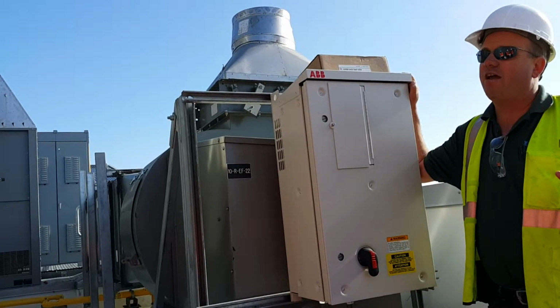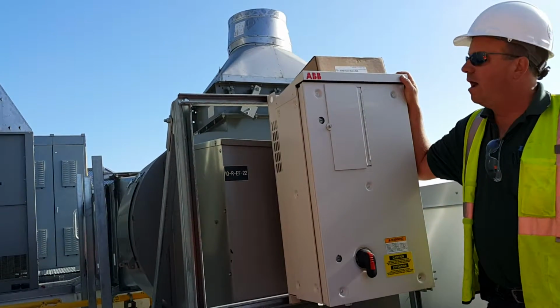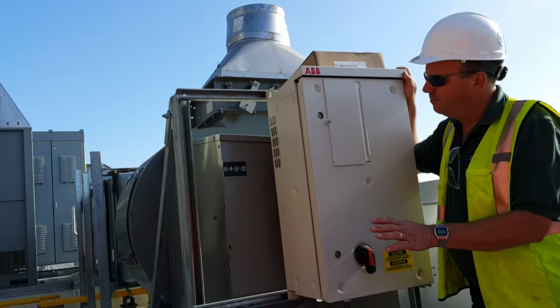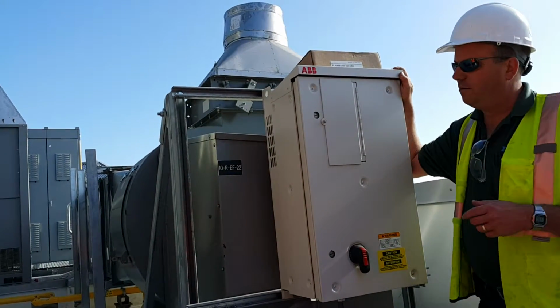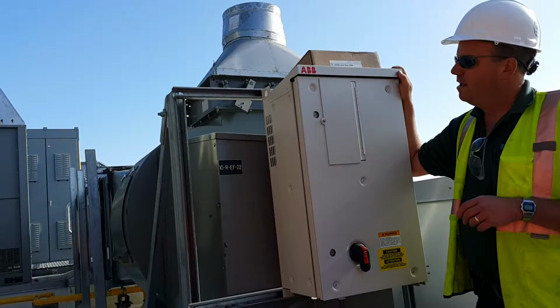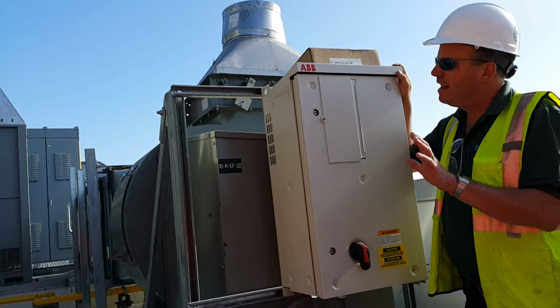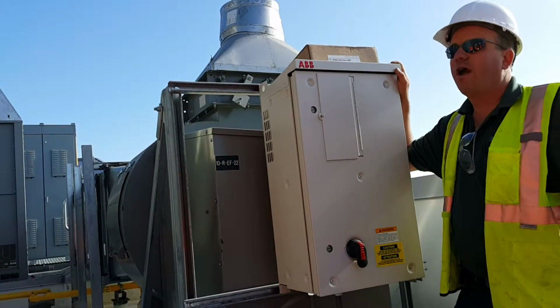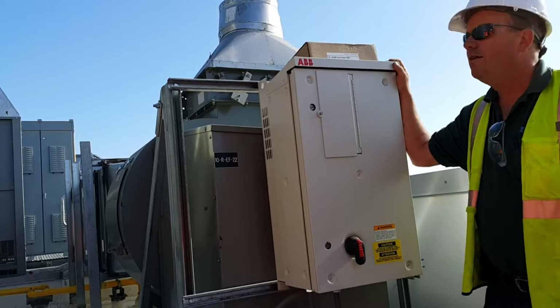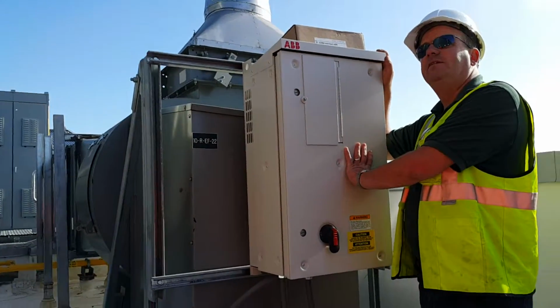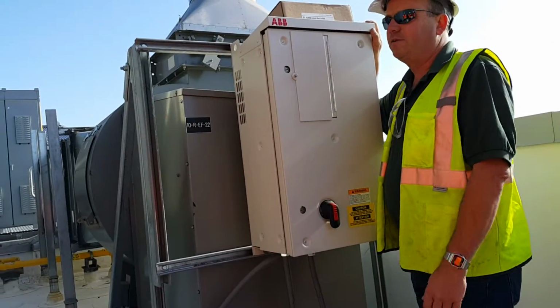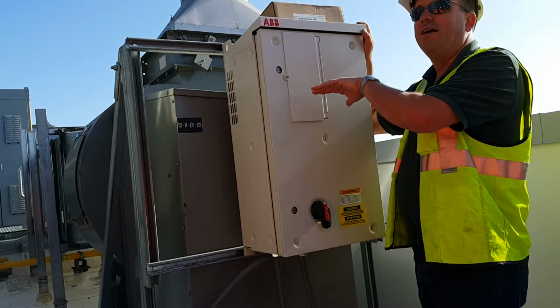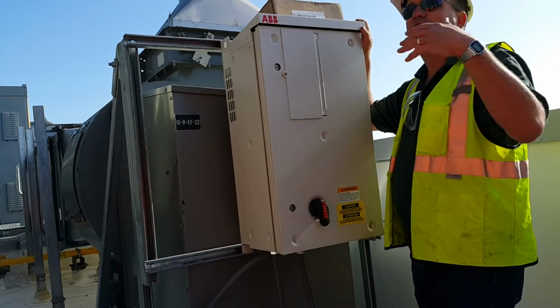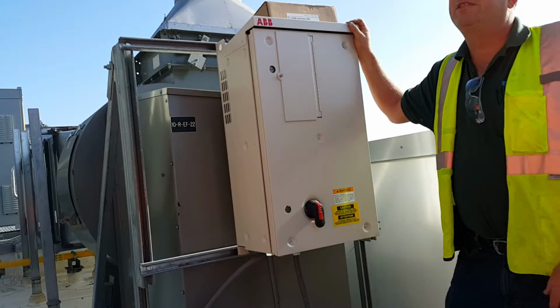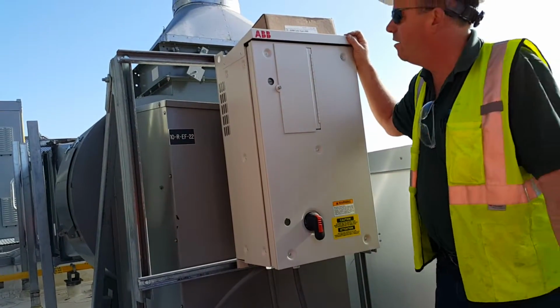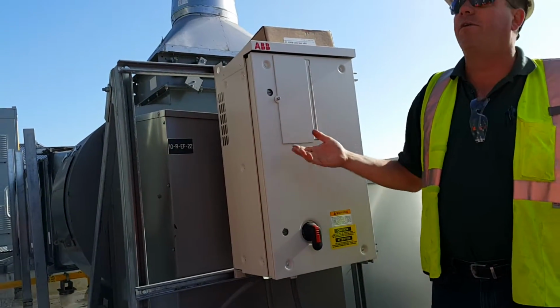just because it's a drive and people get freaked out. It's probably getting a little better now. People get a little more familiar with the basic troubleshooting. So a lot of times I'll go out there and they'll say, oh, the drive faulted and shut down. And I get out there. What's nice about the 550s that previous versions and other manufacturers don't have is the date and time on there. Because it would just record a fault, but you don't know if that was from 5 or 6 years ago. So I've come out to jobs and said, okay, your last fault was an earth fault.